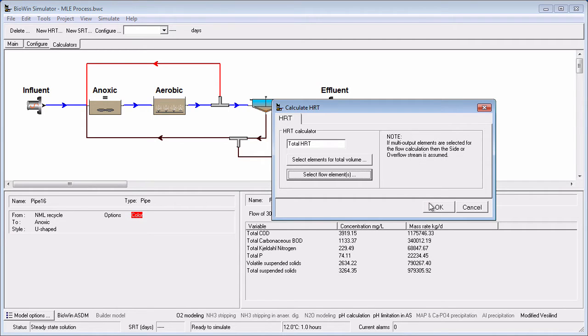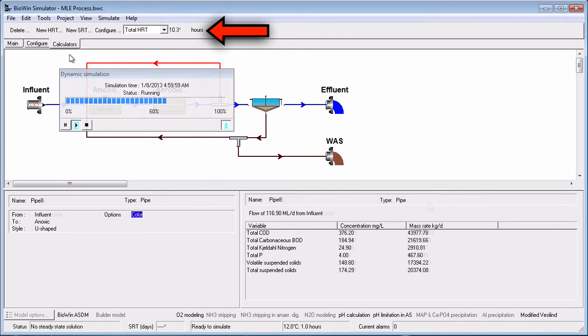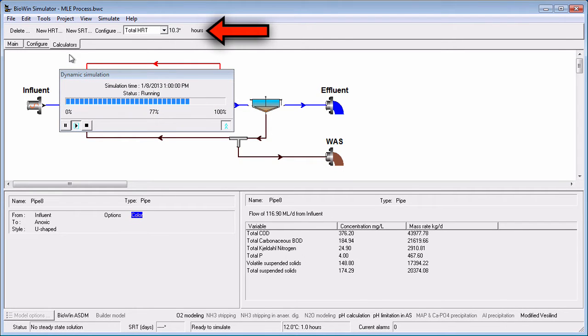If the model is at a steady-state solution, the HRT will be displayed next to the retention time calculator selection list in time units of hours. If you have a time-varying influent pattern, the average flow will be used in the steady-state HRT calculation. If you run a dynamic simulation with varying flow or volumes, the instantaneous HRT will be periodically displayed with an asterisk next to it.